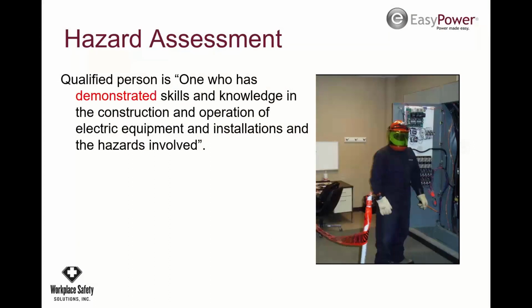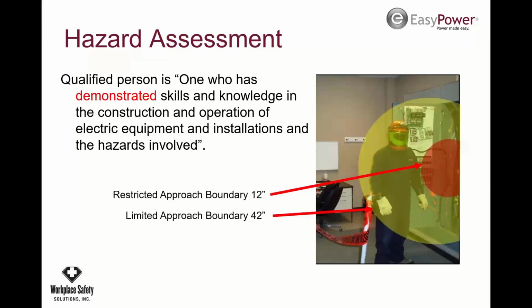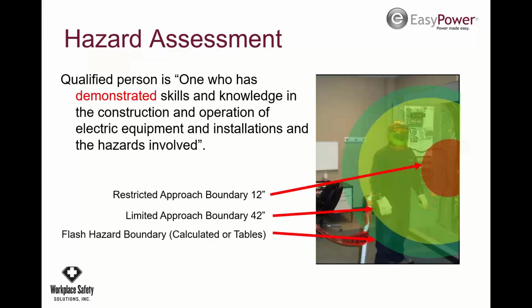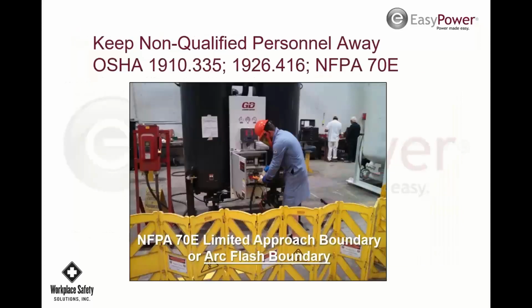So qualified people generally need to know what their shock boundaries are, restricted and limited approach, but they need to know the arc flash boundaries too. So they've got to figure out, by using labels or tables, what that arc flash boundary is. And it's always a good idea for qualified people to look at the report and understand what's on the report and what the issues are that have occurred, and if there are over-duty breakers, things like that, other risky situations. We also have to barricade, so we have to know what that arc flash boundary is before we can throw that barricade out there.